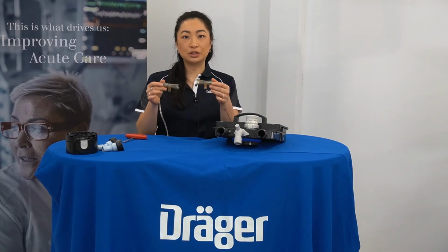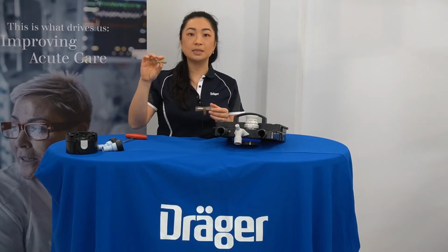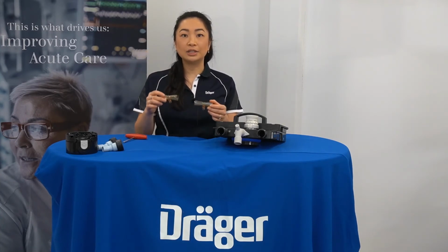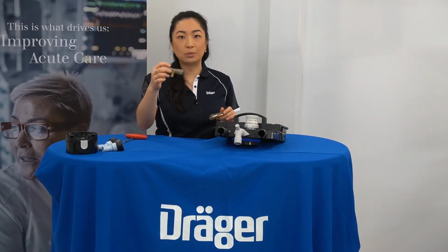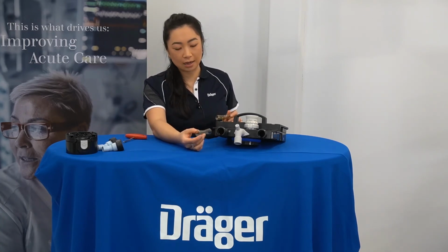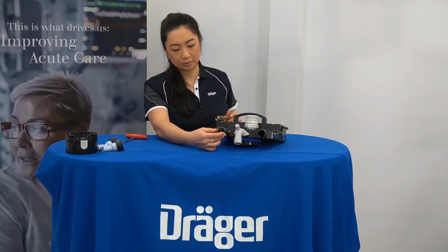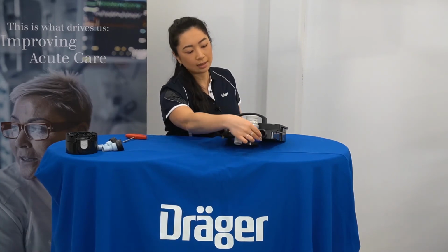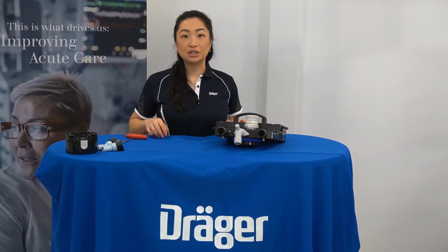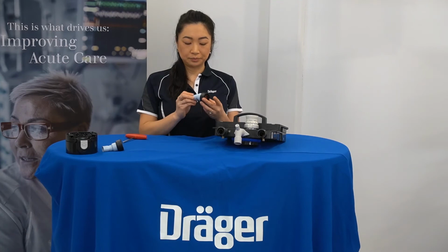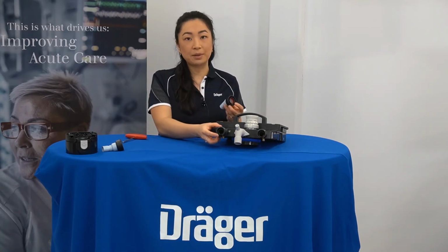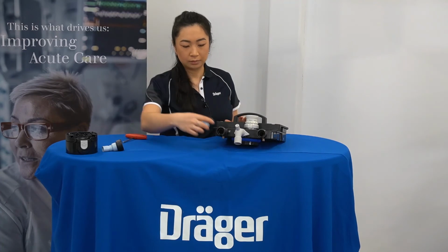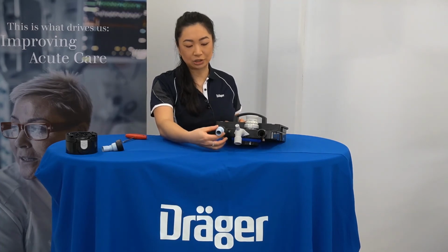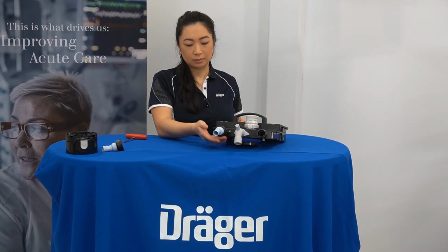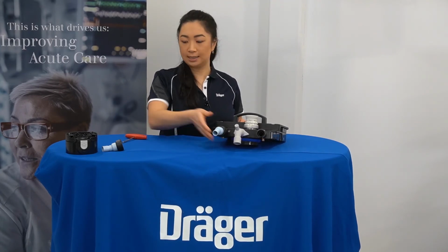Now to return the 2 clean Spirolog flow sensors. Visually inspect the integrity of the wires prior to reinsertion. Then, ensuring the gold wires are pointing downwards, align this up with the gap in the side of the breathing system and sliding them in. Then to reattach the ports, align the notch up with this same gap on the side of the port. Note, these ports are interchangeable. And screwing them on so that they are finger tight.